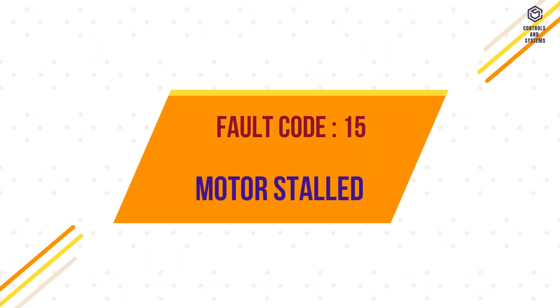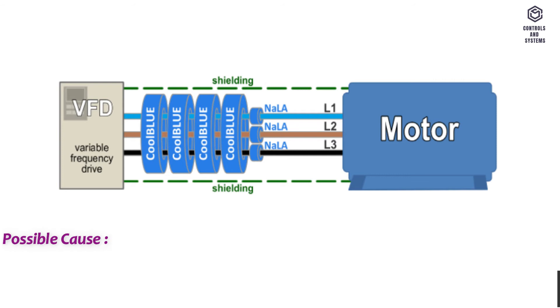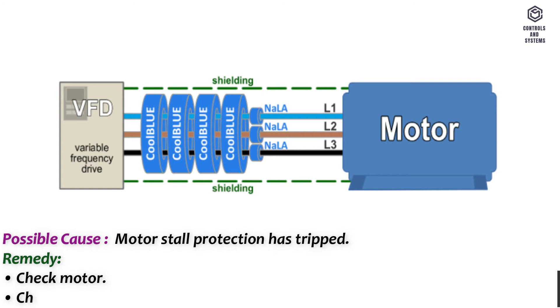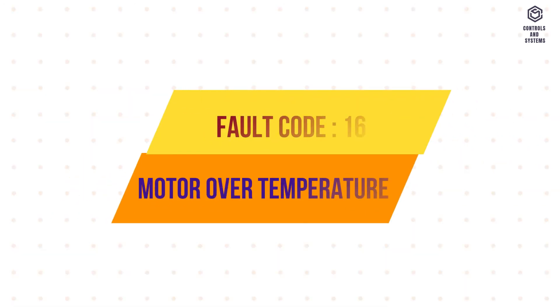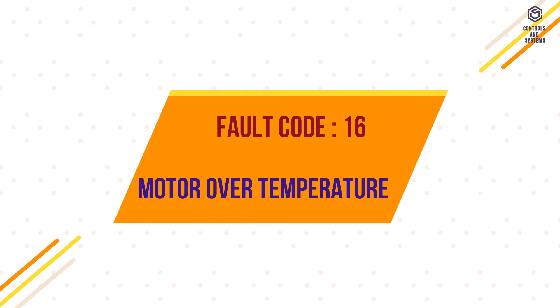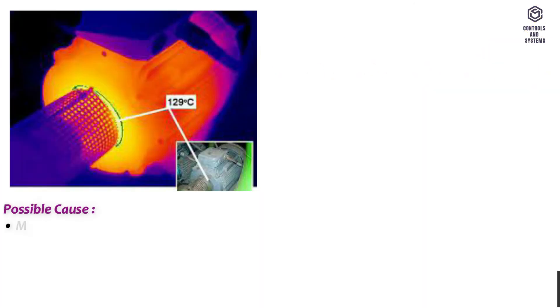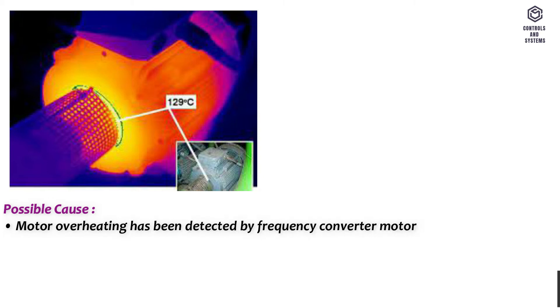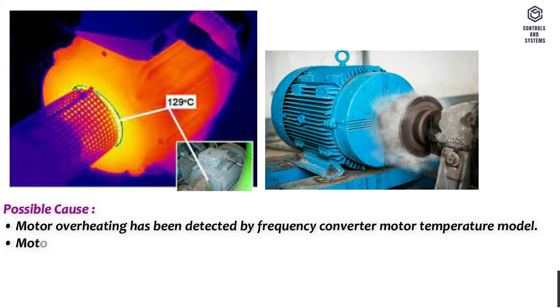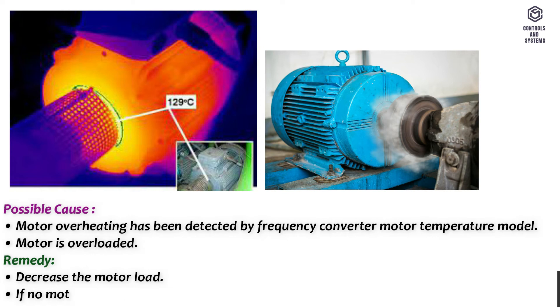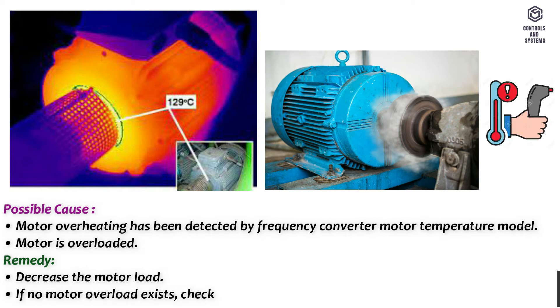Fault code 15 – Motor stalled. Possible cause: motor stall protection has tripped. Remedy: check motor, check that the pump or fan is not blocked. Fault code 16 – Motor over temperature. Possible cause: motor overheating has been detected by the frequency converter motor temperature model; motor is overloaded. Remedy: decrease the motor load. If no motor overload exists, check the temperature model parameters.